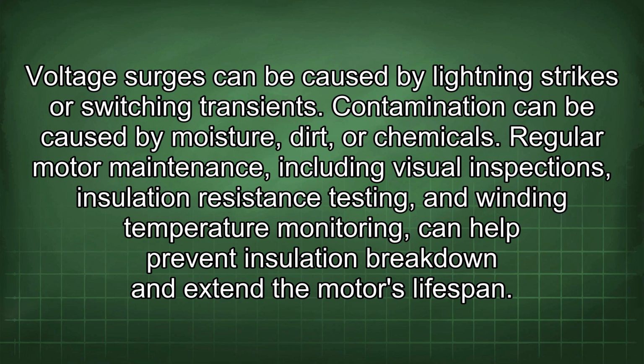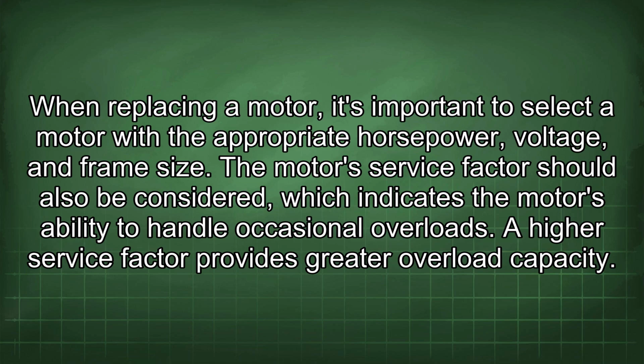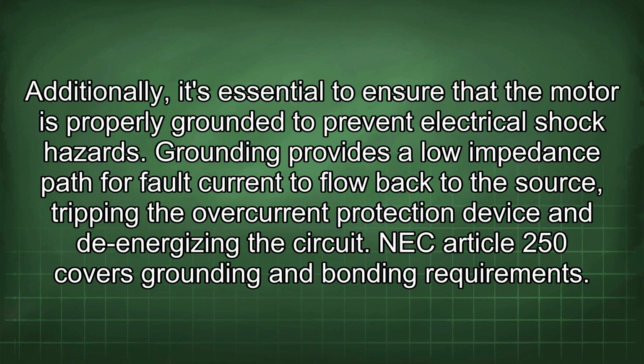When replacing a motor, it's important to select a motor with the appropriate horsepower, voltage, and frame size. The motor's service factor should also be considered, which indicates the motor's ability to handle occasional overloads. A higher service factor provides greater overload capacity. Additionally, it's essential to ensure that the motor is properly grounded to prevent electrical shock hazards. Grounding provides a low impedance path for fault current to flow back to the source, tripping the overcurrent protection device and de-energizing the circuit. NEC Article 250 covers grounding and bonding requirements.